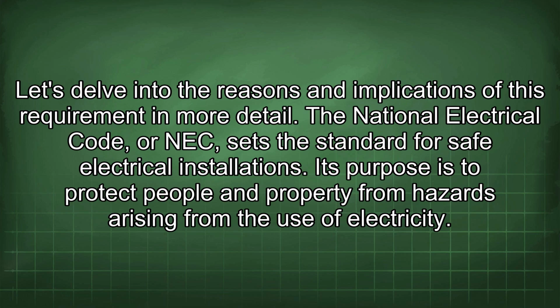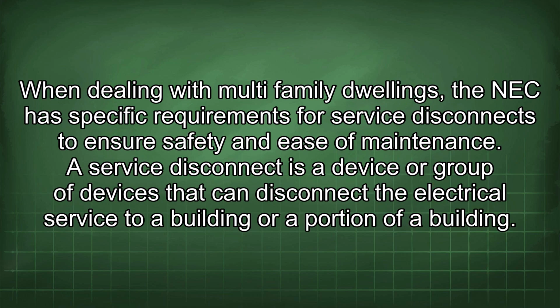The National Electrical Code, or NEC, sets the standard for safe electrical installations. Its purpose is to protect people and property from hazards arising from the use of electricity. When dealing with multi-family dwellings, the NEC has specific requirements for service disconnects to ensure safety and ease of maintenance. A service disconnect is a device or group of devices that can disconnect the electrical service to a building or a portion of a building.